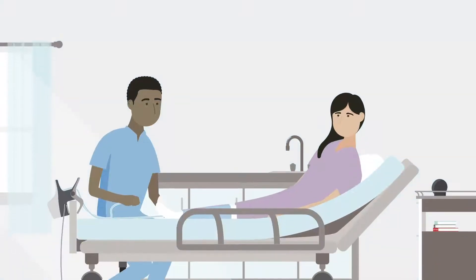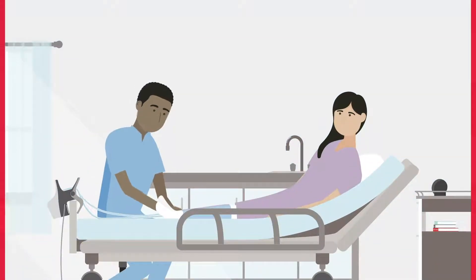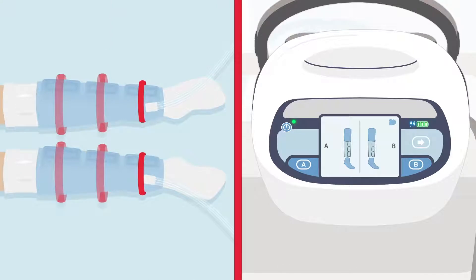Once the pump is turned on and the sleeves or foot cuffs are properly positioned, the controller will go through 5 to 10 compression cycles to detect the patient's presence and continue to check every 30 minutes.